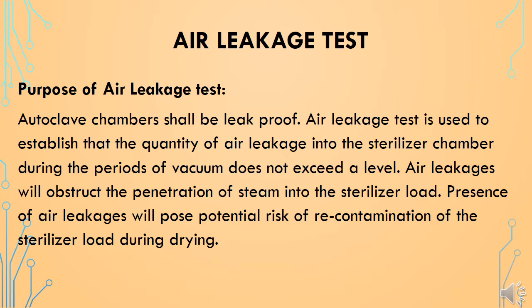The next qualification test is air leakage test. Autoclave chambers must essentially be free from leaks, so the air leakage test is done to find out any leakages from the chamber. It is used to establish that the quantity of air leakage into the sterilizer chamber during the period of vacuum does not exceed acceptable levels. Air leakages will obstruct the penetration of steam into the sterilizer load and pose a potential risk of recontamination of the sterilizer load during drying.